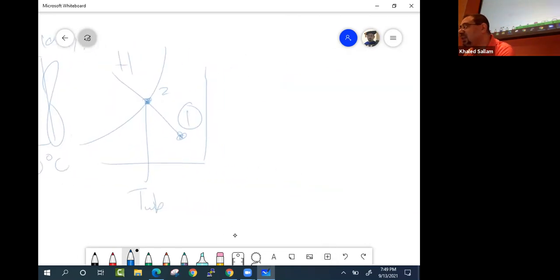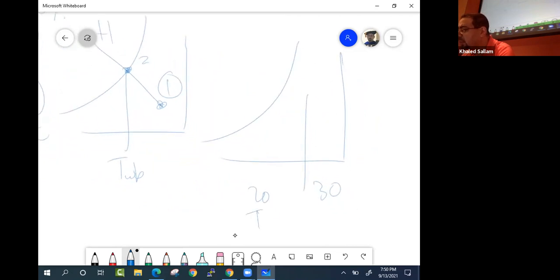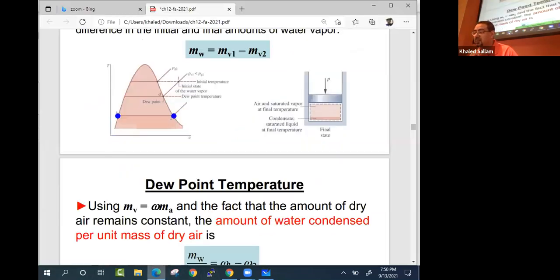Knowing your wet bulb and dry bulb, you can find where you are. Say you're at 30 and 20: T wet is 20, T dry is 30. How do I find my phi, my W, my H? You go at 20, go up, then move at constant H, and that's your point. So knowing the dry bulb and wet bulb, you can find where you are on the curve. Make sense?